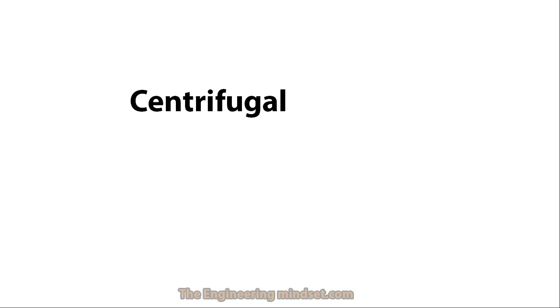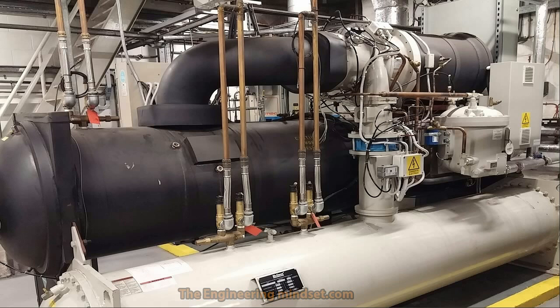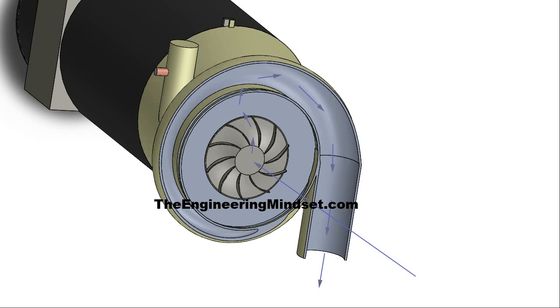The first one we're going to look at is the centrifugal type compressor. It looks a lot like this, and it's quite easy to spot because it's got this large unit up on the top of the chiller. You've got the suction line coming off the evaporator and flowing into this volute shape, and then off of that the refrigerant flows down into the condenser. The refrigerant flows in through the suction line and hits into the impeller blades.